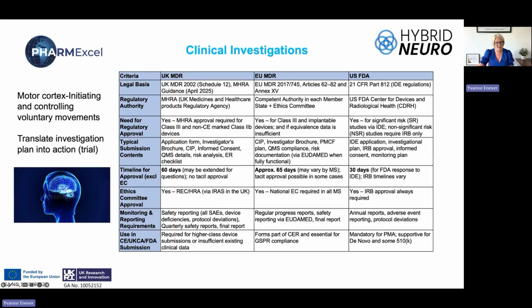The typical submission contents are fairly similar between the different authorities. You'll need your application forms. You'll absolutely need to have an investigator's brochure in place, because you've got an investigational device. So your investigator's brochure will have lots of your preclinical elements in. You'll need to have your clinical investigation plan, so your CIP, in place, so essentially your trial protocol. You will certainly have to have all your quality management system details identified. Your risk analysis will need to be in there, and essentially your essential requirements or your safety and performance checklists will need to be in there as well.